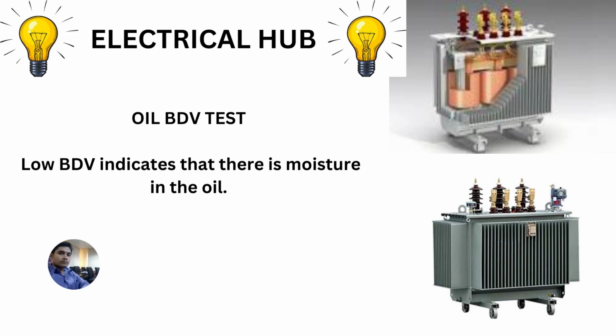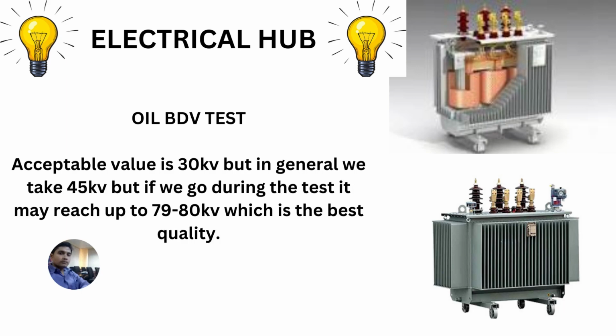What is the difference between the IEC and the European standard? According to the IEC standard, it is done with a gap of 2.5 mm, but according to the European standard, it is done at a 2 mm gap. What is the acceptance value? The acceptable BDV value of the oil is 30 kV, but in the industry we generally accept 45 kV. While we do the test, it goes up to 79 to 80 kV, which is, of course, the best result.